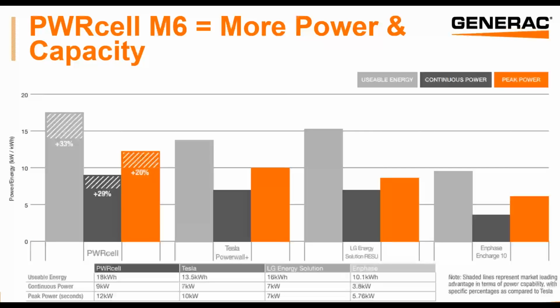From a technology perspective, our M6 is our flagship battery. That's when you're stacking 6 battery modules in our battery cabinet. That offers 18 kilowatt hours with 9 kilowatts max continuous power. So it's extremely powerful when you need it to be, and the capacity sits at a place that'll get most homeowners through the night in an outage.